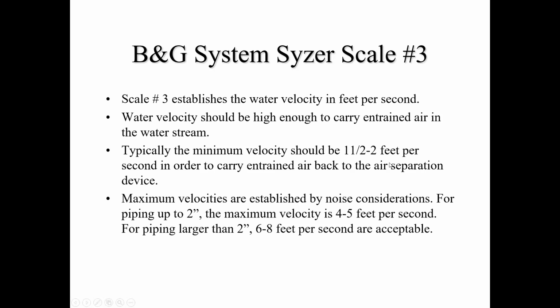You get into commercial settings, manufacturing, where there are other noises, and so noise isn't your concern. It's just that I don't want to erode the pipe because my velocity is too high, erosion through corrosion. So I'll have a high side. Where noise is a concern, the scale says 2-inch, but it can apply to larger diameter pipe. It's more the application. Typically, you don't want to be beyond 4 to 5 feet per second on the high side for noise. For larger pipe or a more commercial setting where there are other noises, so noise is off the table as a concern, typically around 8 feet or so per second.